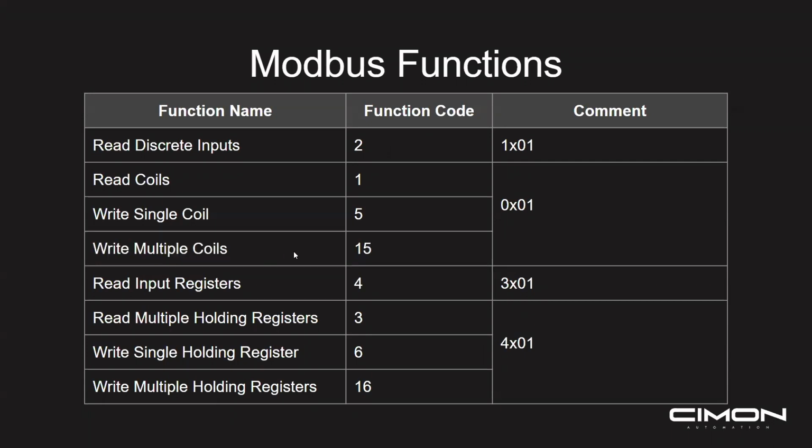The reason I put this slide up is to show you that we do not support multiple coil writes with the PLC software. You have to remember, this presentation I'm showing you right now is oriented for our PLC. So we do not support multiple coil writes on the PLC, so you'd have to develop multiple frames for writing a single coil. But we do support writing multiple words at the same time with the ModBus protocol. So anyway, these are the different functions that we support.